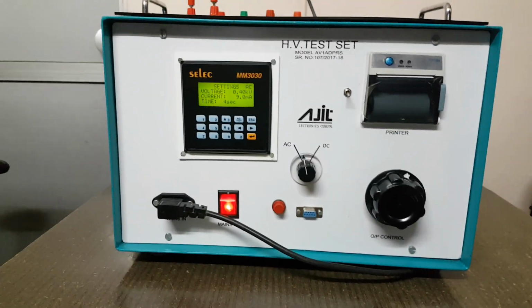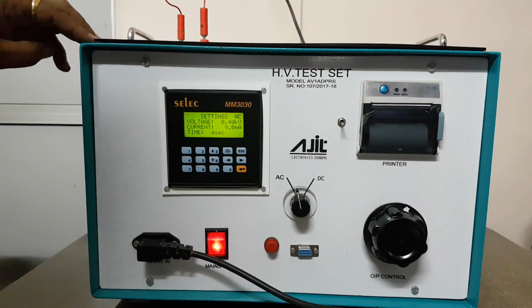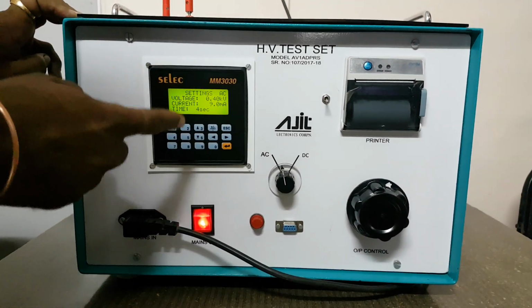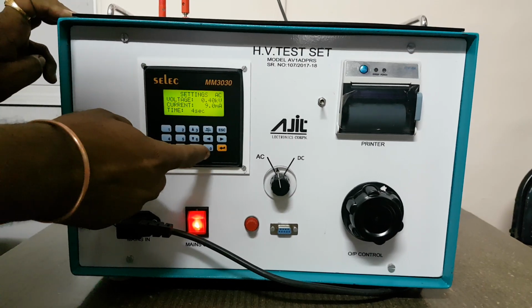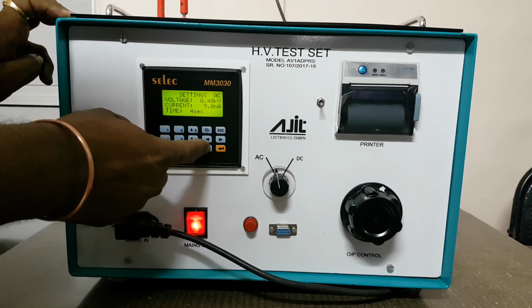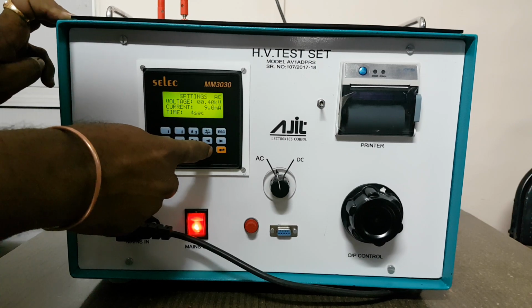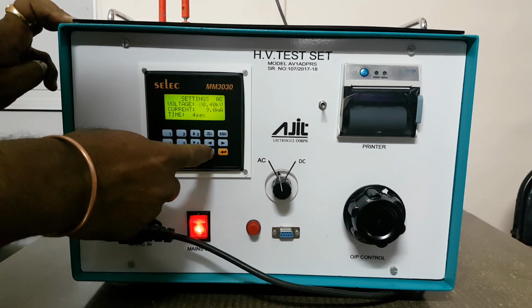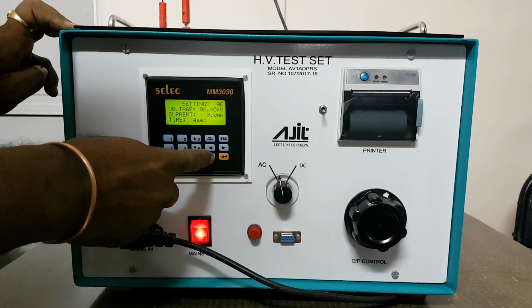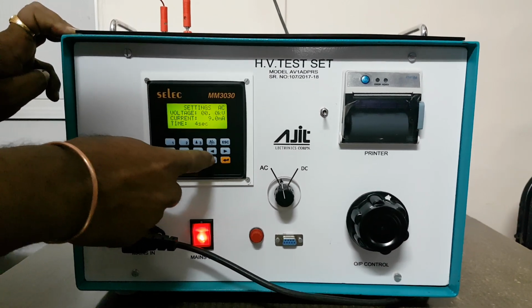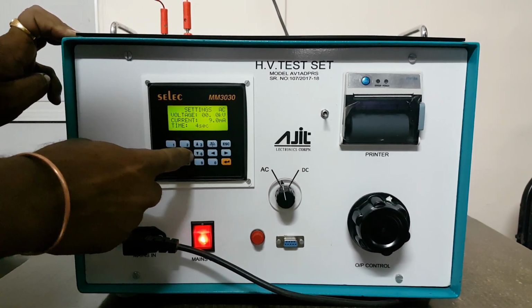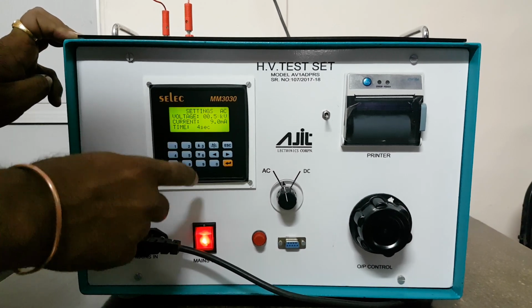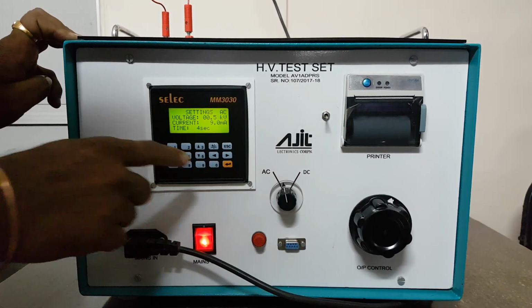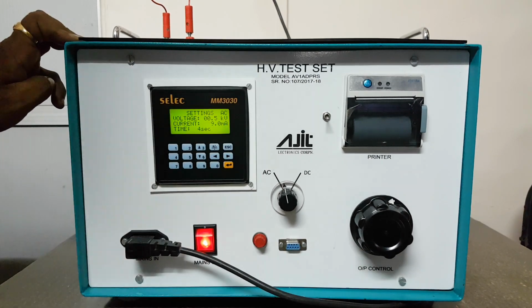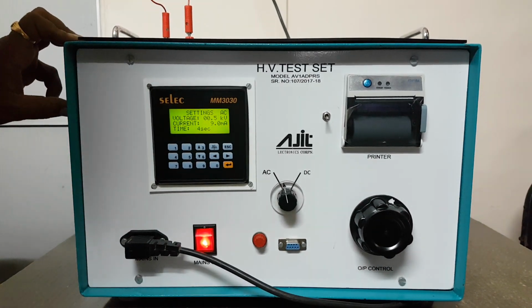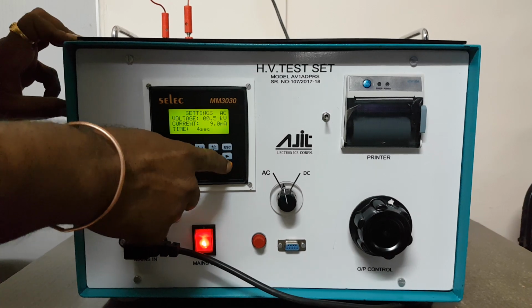Now here we can set the output test voltage. By default, it is showing 0.4 kV. Let's say 0.5 kV. For that press 0, again 0, it will shift to the next digit, again 0, it will shift to the required position. Then we want 0.5 kV. Once all the digits are set properly, press the enter key.